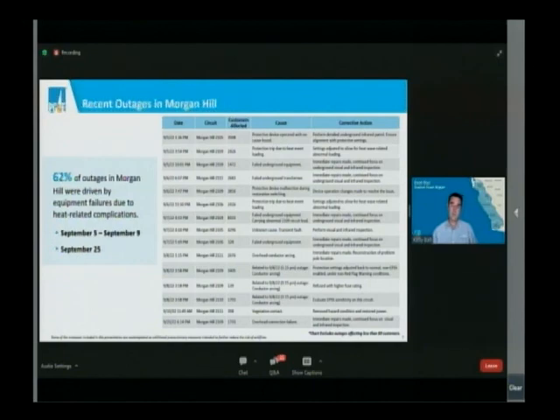And I believe the second part of that question was, why did the 2109 fail several times? And I asked for this slide to be brought back up again because I did want to show this one again. So if we look at the circuit column here, there are a number of issues that happened, and they happen to be on the Morgan Hill 2109 circuit. So there was a heat event, there was an overloading due to heat, just overloaded equipment that relayed open. The next one down, we had failed underground equipment.